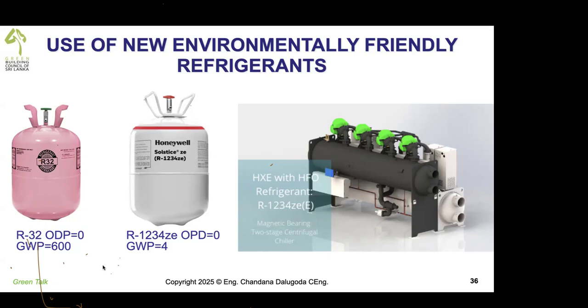Now, then they introduced HFC refrigerants, hydrofluorocarbon refrigerants, with ozone depletion 0. So until today, we can't use a refrigerant with higher ODP. ODP, ozone depletion potential, should always be 0. But now, very lately, we found that just because ozone depletion is 0, there's another problem called global warming. So the term is global warming potential, which has to be low.